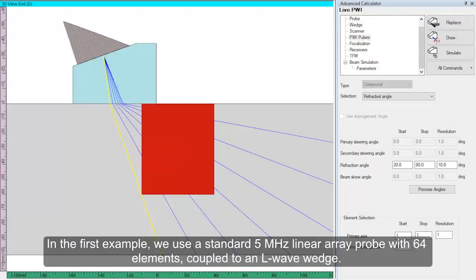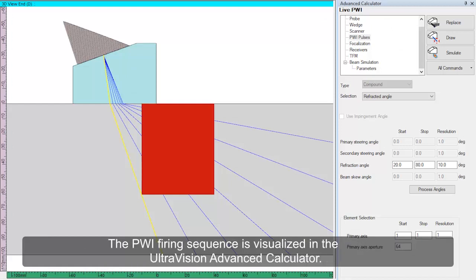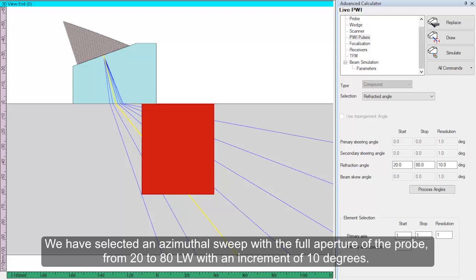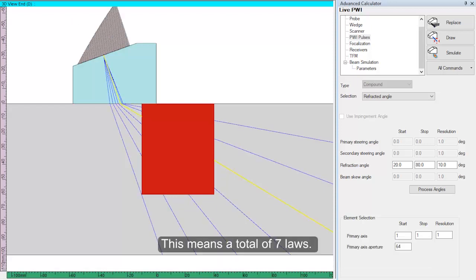In the first example, we use a standard 5 MHz linear array probe with 64 elements, coupled to an L-wave wedge. The PWI firing sequence is visualized in the UltraVision Advanced calculator. We have selected an azimuthal sweep with the full aperture of the probe from 20 to 80 degree L-waves, with an increment of 10 degrees. This means a total of 7 laws.